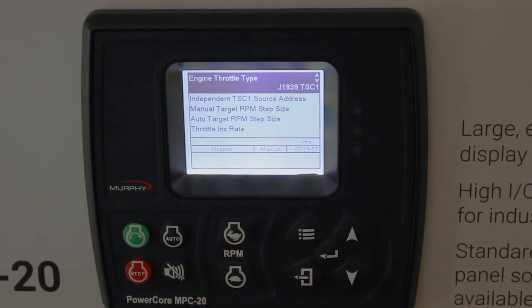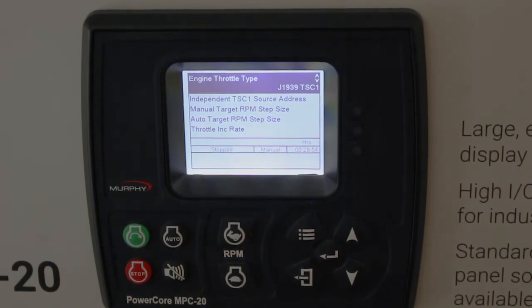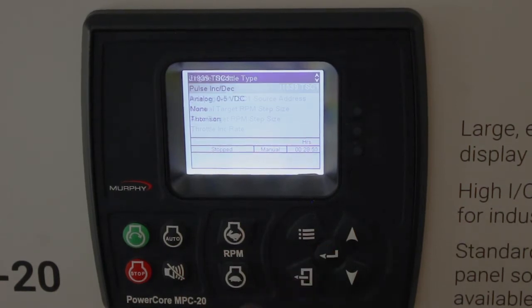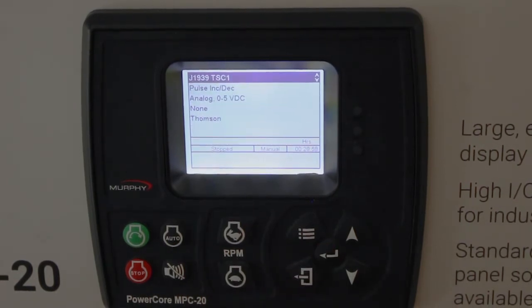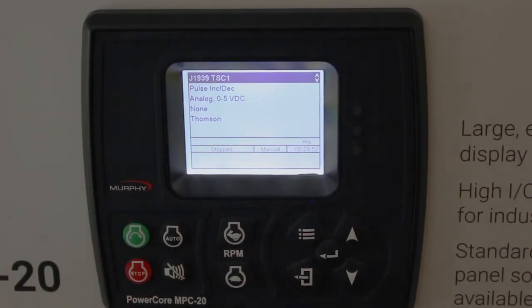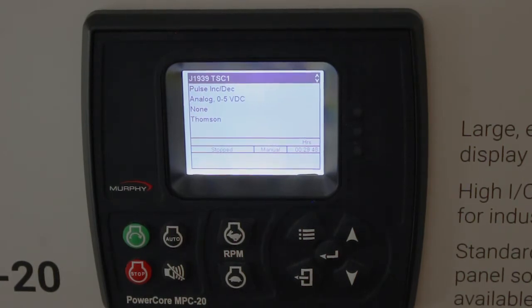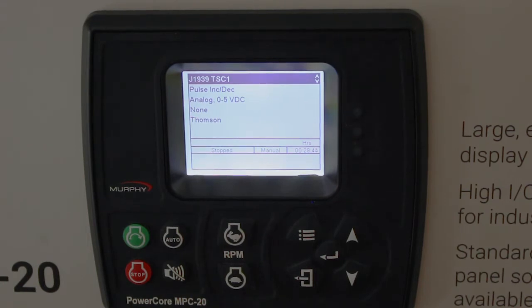Engine throttle type is the first item. It defaults to J1939, which is TSC1 throttling. If you hit enter, you have all kinds of choices for mechanical engines and even a Thomson actuator that operates on proprietary CAN messaging. So you can have Pulse Inc/Dec for our throttle actuator, analog output, or no throttling.